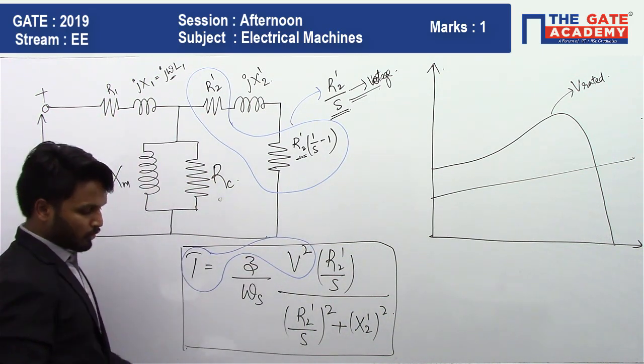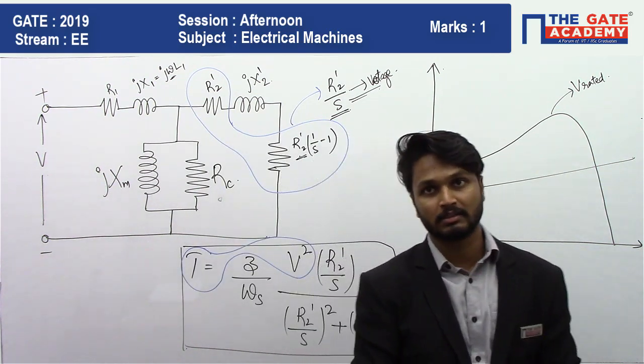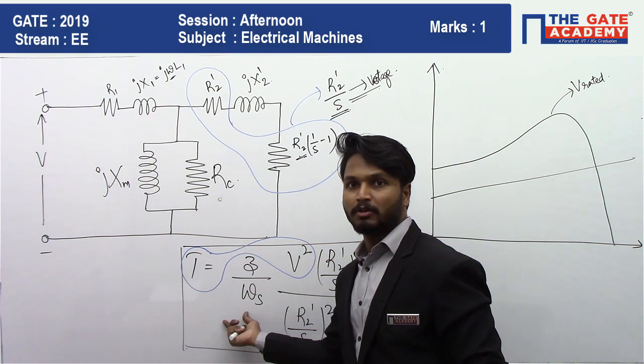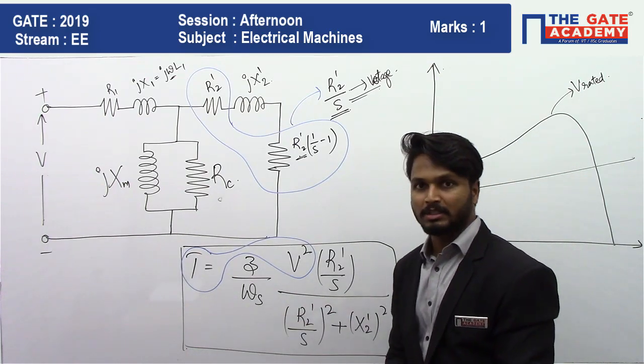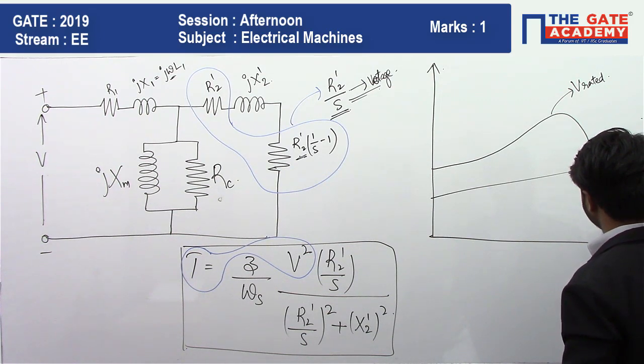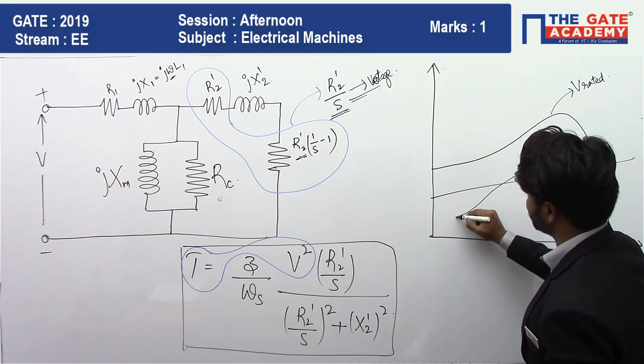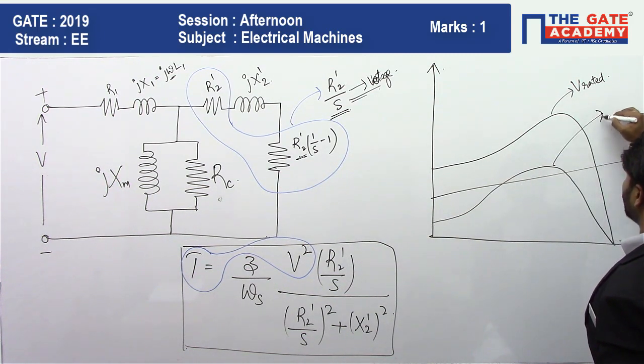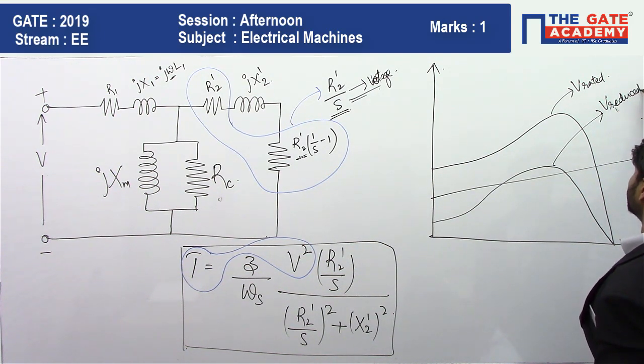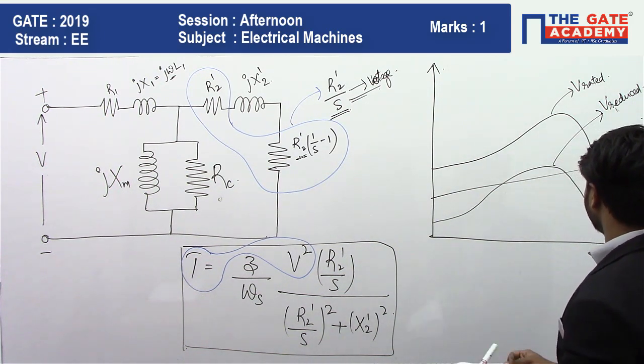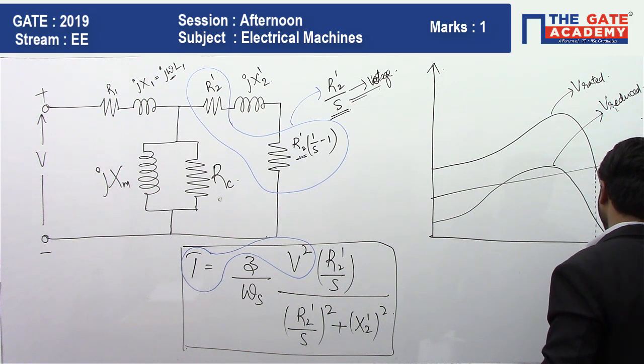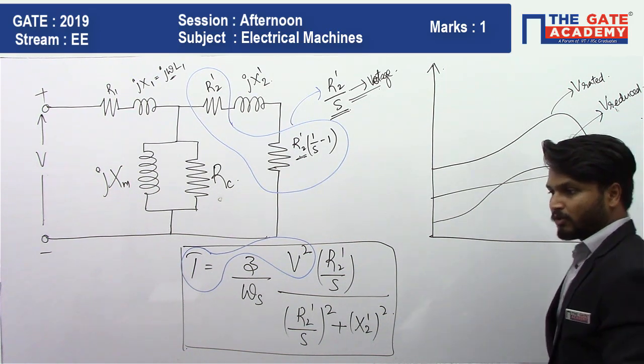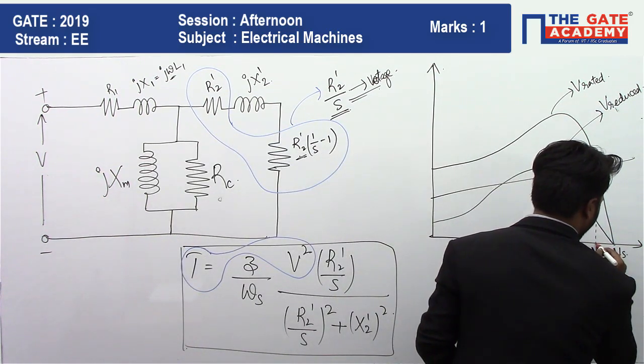If we decrease the voltage, torque decreases. The synchronous speed is purely dependent on frequency and remains the same. So when voltage is reduced, the torque-speed characteristic shifts downward. The new operating point moves such that the rotor speed decreases. Previously the rotor speed was Nr; now it becomes Nr dash, which is lower. The slip, which is the difference between synchronous speed and rotor speed, has now increased.